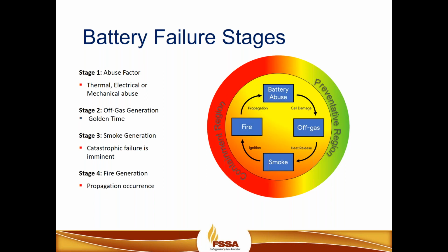In many different types of applications, we've used early warning detection, such as air sampling, smoke detection, say in mission critical type facilities like data centers, telecommunication, in different types of applications. But in particular to lithium ion batteries and energy storage systems, by the time we reach the smoke generation stage, it's too late. Thermal runaway occurs at the same time that smoke generation occurs, and it cannot be prevented.